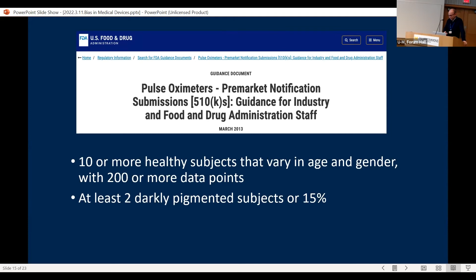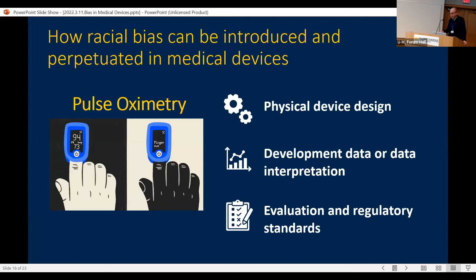So in summary, how was racial bias introduced and perpetuated in pulse oximeters? There were issues with the physical device design. There were assumptions that, when you isolate the peak and trough of the wavelengths of the cardiac cycle, you can get away from having influence on things like skin pigment. The development data was problematic because it's likely the case that when pulse oximeters were first developed, they largely used white male patients to calibrate these devices. So of course they work better on white male patients than on other patients. And then the evaluation and regulatory standards were insufficient.